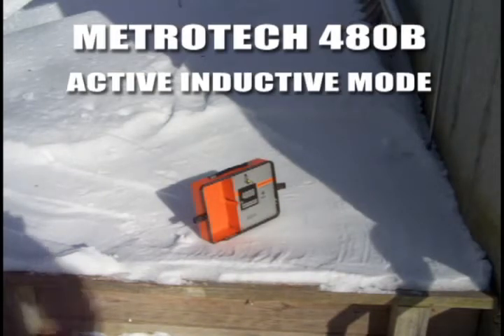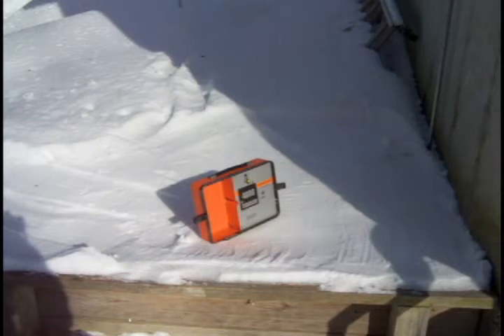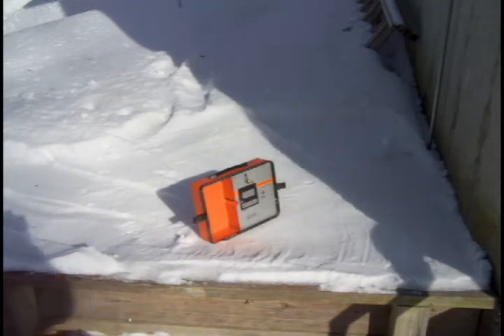This is a demonstration of a Metrotech 480B. I have placed the transmitter over an underground power cable, about two feet down. This is inductive mode, where the signal is being emitted from the metal ring around the case and is inducing a magnetic field into the earth, causing an electric field to be generated along the cable. I'm going to use the receiver further down the line, maybe 150 feet.